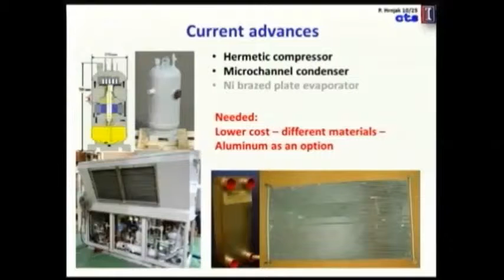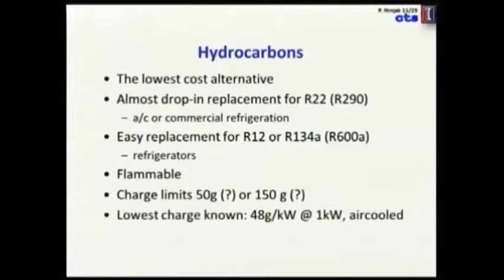Now hydrocarbons are definitely the lowest cost alternative—almost a drop-in replacement: R290 for R22, and for R12, R134A, and so on. Flammability also brings charge reduction to a higher level, down to 50 or 150 grams. I'm aware of the lowest one, 48 grams, which was in the public domain, which we did for a 1 kilowatt bottle cooler, and it worked very nicely.